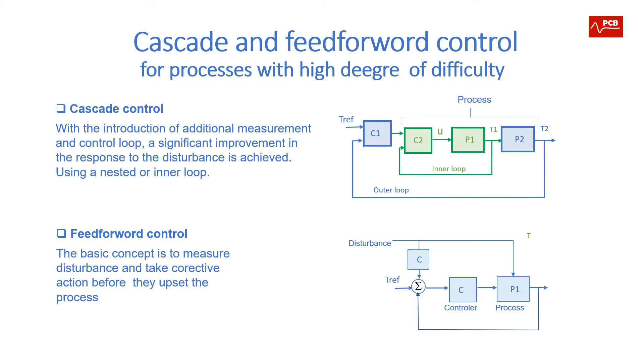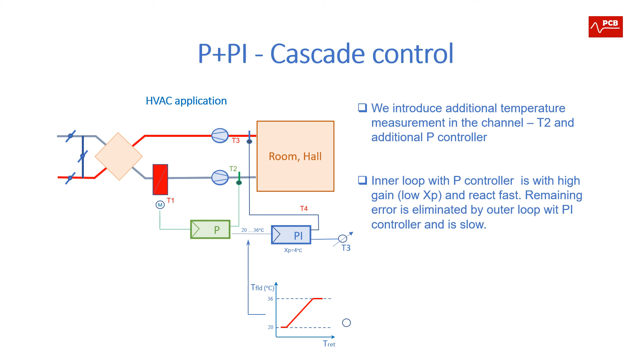In practice, in air conditioning processes like this, we introduce an additional temperature measurement in the channel. It is T2, and an additional controller, which is usually P-type, and we have an inner loop with a P controller, and this controller has very high gain or a very low proportional band, and the input as a reference to this controller is the output from the PI controller, which completely eliminates an error on the controlled parameter, which is T3 in our case.